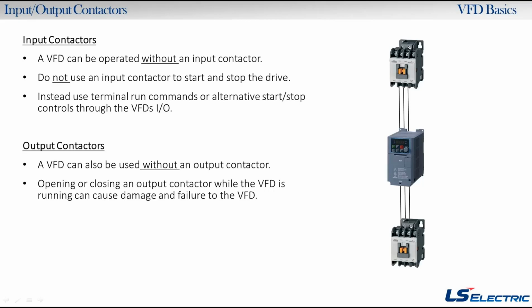Because opening or closing a contactor when the VFD is running and outputting voltage could damage those transistors on the output, and then it could cause a short, and just like the other stuff, the drive's not going to work anymore.